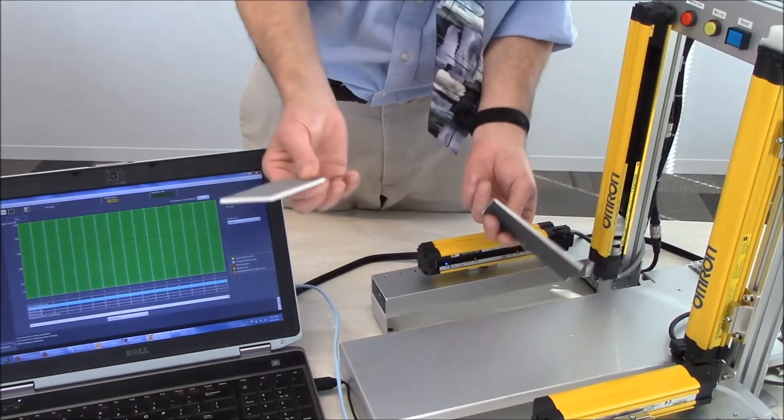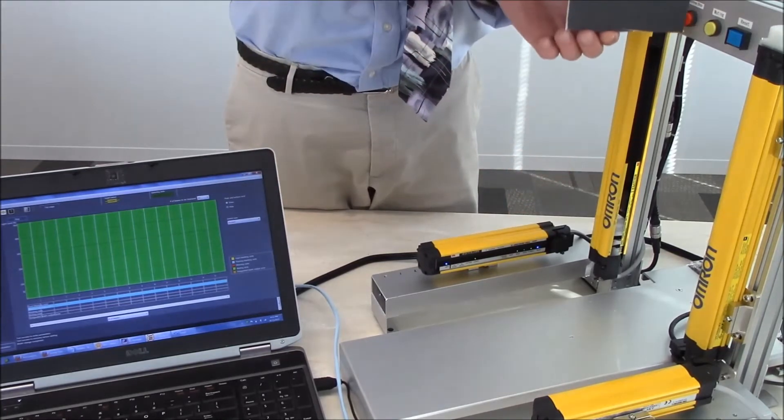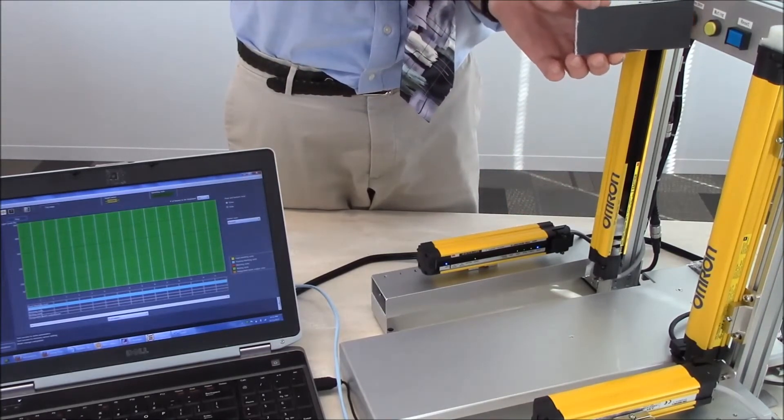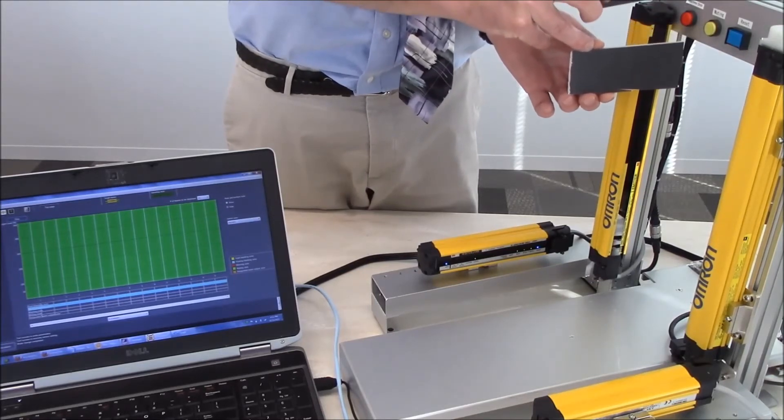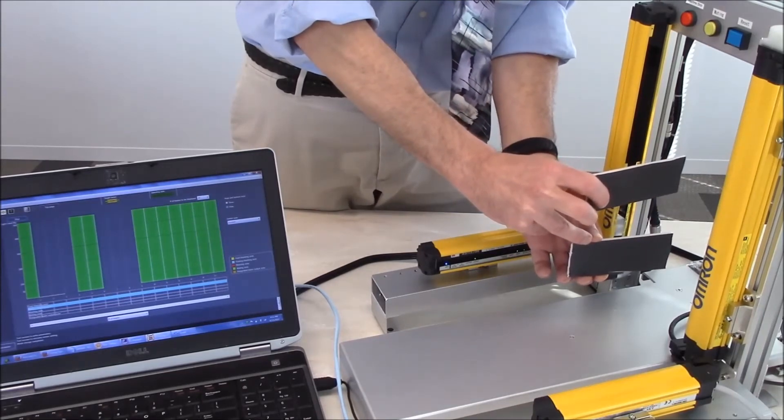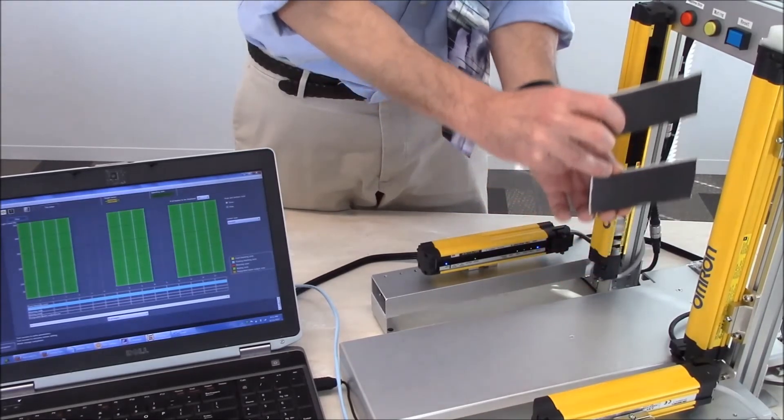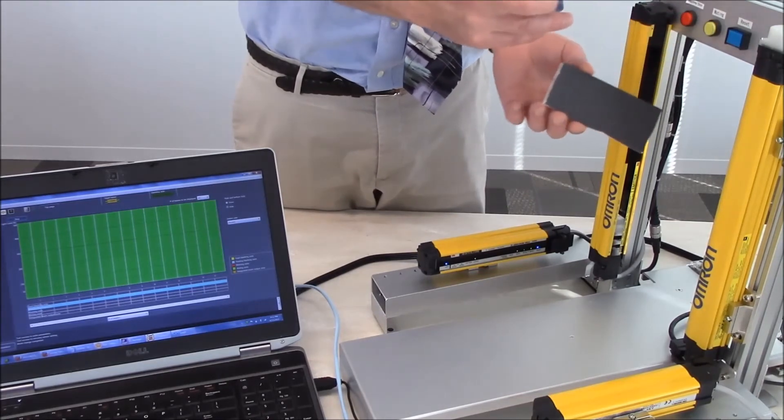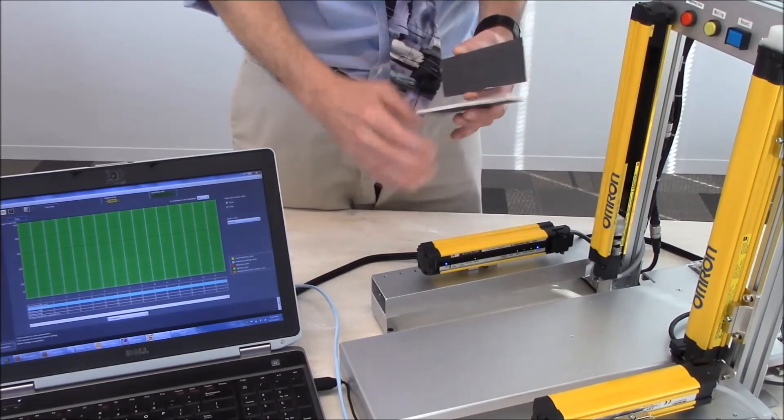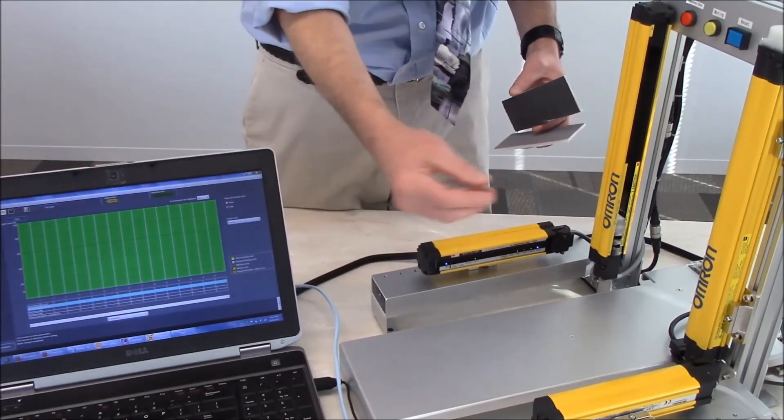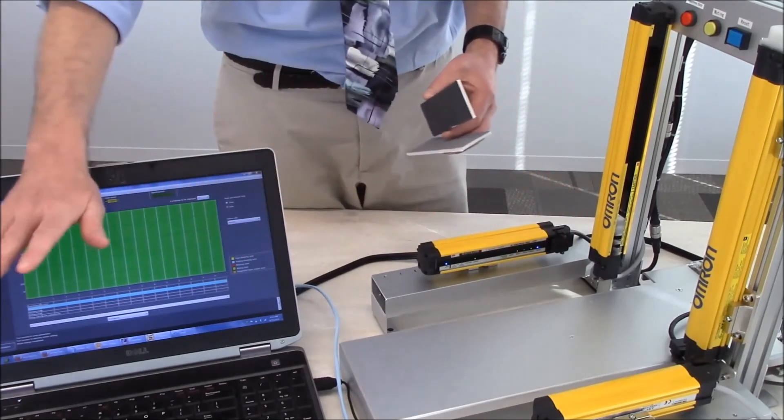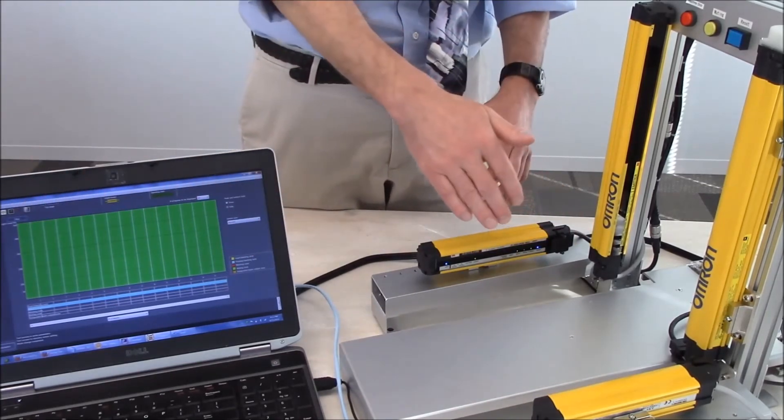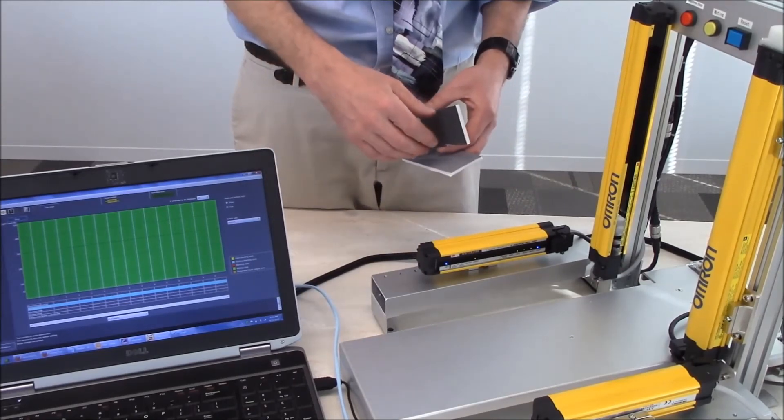So the thing that is nice about this feature is, let's say that you have a cart that you are moving in and out of the light curtain, like they show in the user manual. If I bring that cart into the area, everything is fine, and then if I move it out, it is fine as well. So if you have your light curtain on the floor and you are bringing an object in, as long as it is less than those 3 beams, you can move it in and move it out. But if a human walks in that area, it is larger than the 3 beams, it will trip the light curtain.